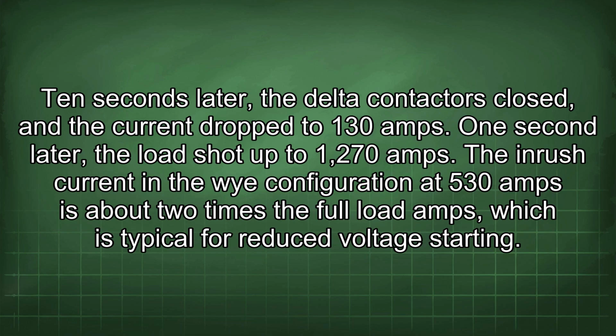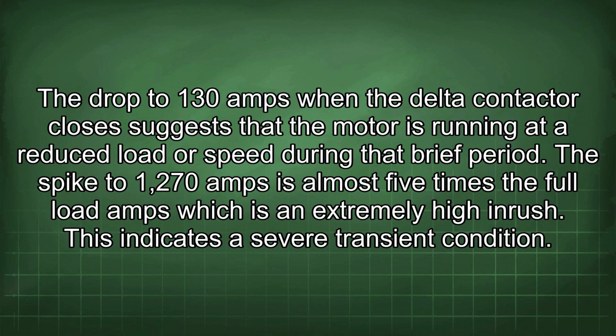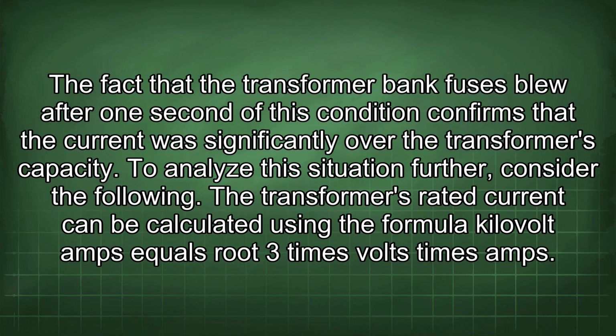The inrush current in the Y configuration at 530 amps is about 2 times the full load amps, which is typical for reduced voltage starting. The drop to 130 amps when the Delta contactor closes suggests that the motor is running at a reduced load or speed during that brief period. The spike to 1270 amps is almost 5 times the full load amps, which is an extremely high inrush. This indicates a severe transient condition.